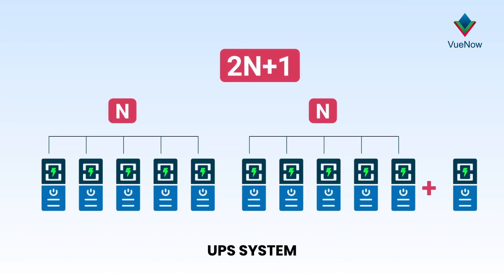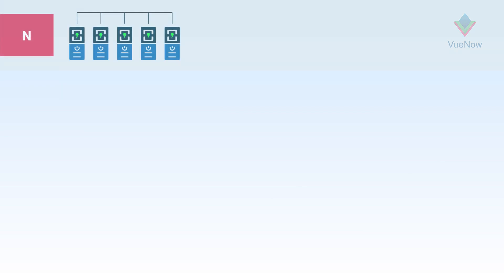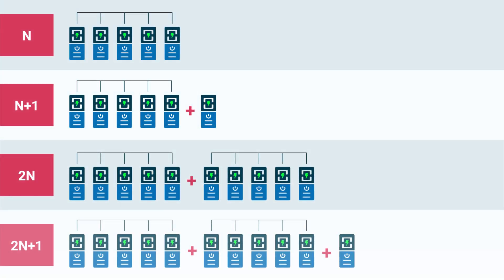2N plus 1: the 2N+1 model takes the 2N model a step further and is the highest obtainable redundancy level. It provides a full set of backup units plus an additional component for extra protection. This configuration can maintain operation in the event of multiple unit failures and withstand an entire primary system shutdown, sustaining N+1 redundancy if a center's main unit loses power or undergoes maintenance.